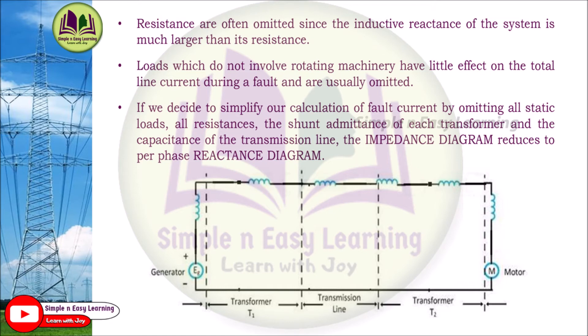Loads not involving rotating machinery — meaning static loads other than motors — can be omitted. A motor is a rotating load and cannot be omitted, but static loads without rotating machinery can be. To simplify fault current calculations, we omit four things: all static loads, all resistance, the shunt admittance of each transformer, and the capacitance of the transmission line. With these omissions, the impedance diagram reduces to a per-phase reactance diagram.